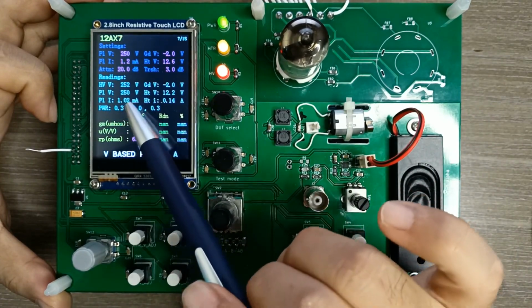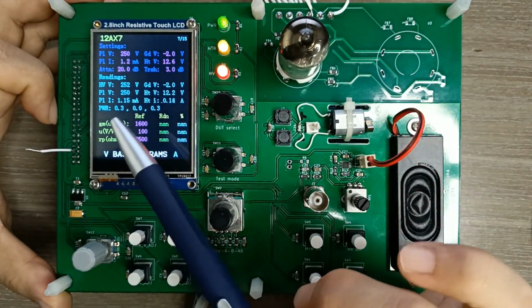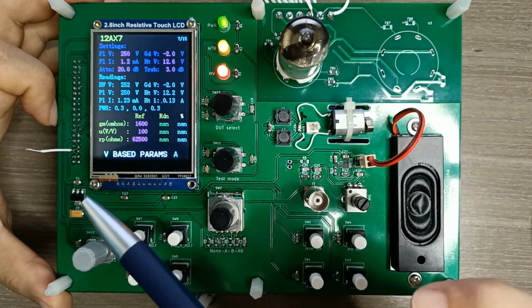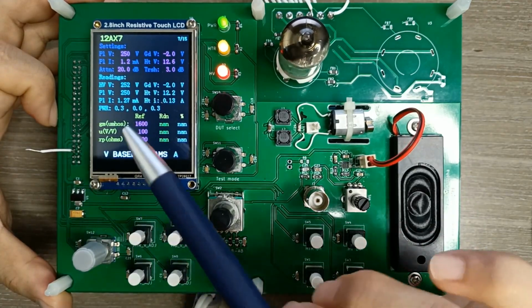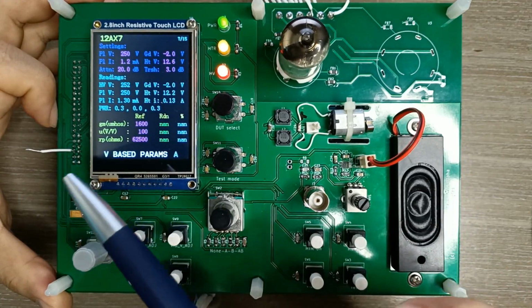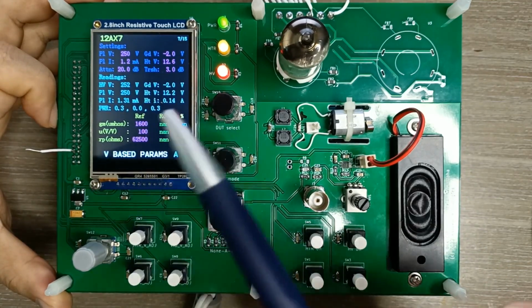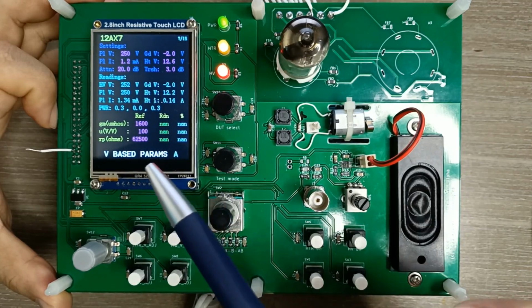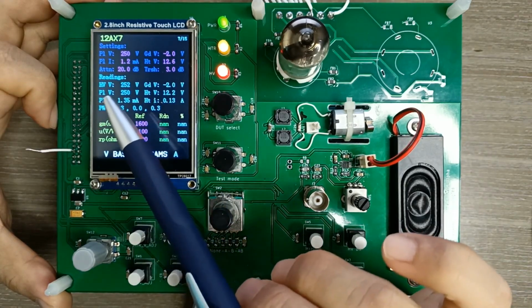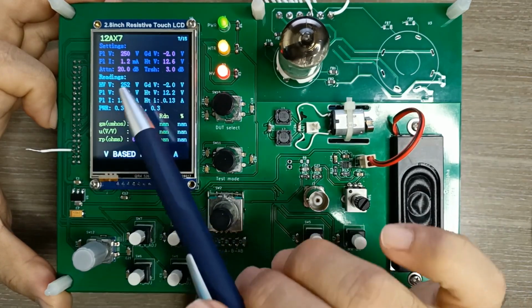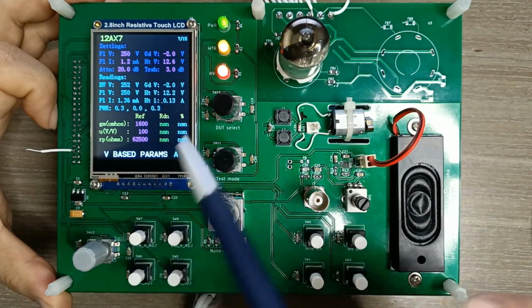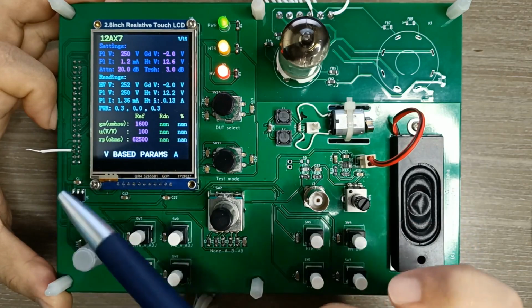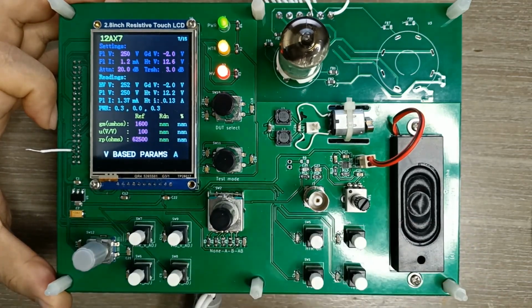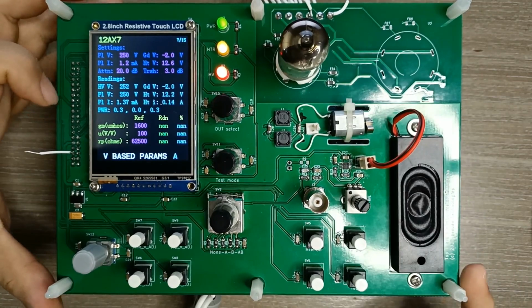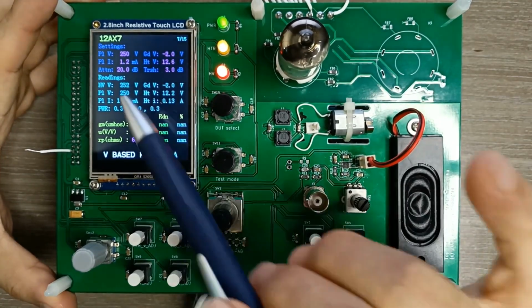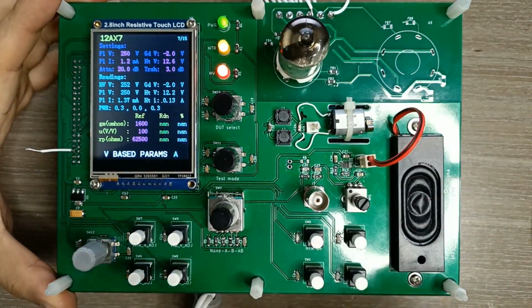They are slightly different. The reason is that after the high voltage supply is generated, it goes through the constant current source and some internal resistance and some transistors. So the actual voltage appearing on the plate will be lower than the high voltage supply. The firmware will automatically adjust the value using an update algorithm to keep the plate voltage set to our desired value.